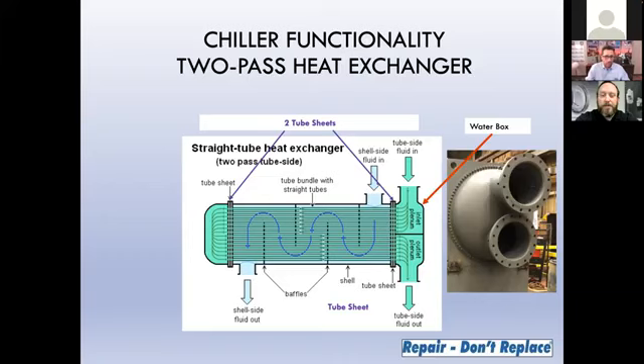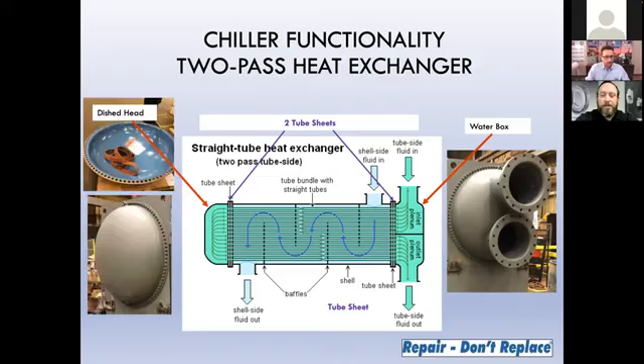There's typically a marine water box on one side of the unit, a dished return head on the other, and two tube sheets on each end of the shell. Water comes into the unit through the inlet side of the marine water box, passes through the tubes, is turned around by the dished return head, and passes through the tubes a second time out of the marine water box. The water passing through the unit two times gives the term two-pass condenser its name.